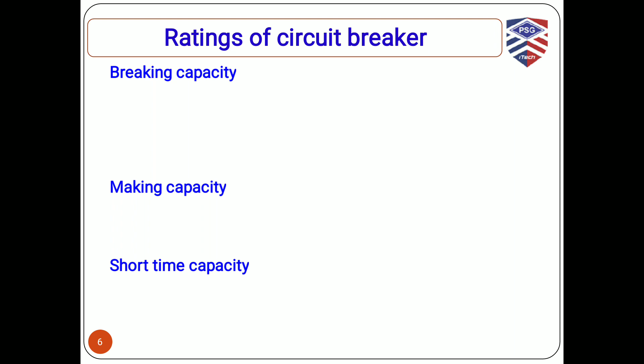Next, we will have a look at different ratings of circuit breaker. Mainly, we'll deal with the breaking capacity, making capacity, and short time capacity. What is breaking capacity? It is the highest current that any circuit breaker can break at a stated recovery voltage under prescribed conditions. It is usually expressed in kiloamps, kA in short. For example, if a circuit breaker is rated for 10 kiloamps short circuit interrupting capacity, it means that the particular circuit breaker can break a current of 10 kiloamps magnitude without any damage to the equipment or circuit.